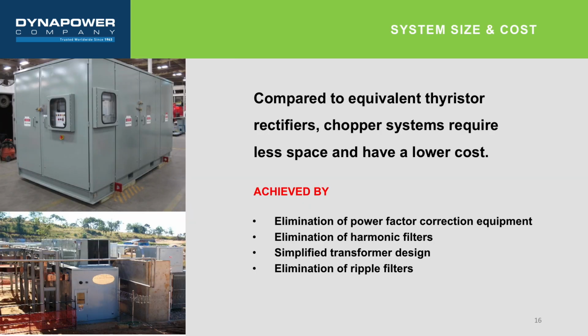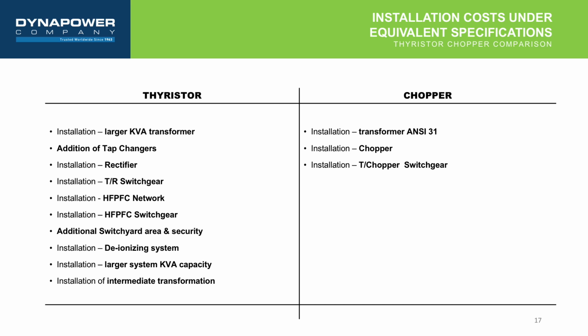System size and cost. Compared to equivalent thyristor rectifiers and harmonic compensation equipment, chopper systems require overall less installation space. A major part of the cost of the system comes from magnetic components, especially the transformer. With the reduction of additional equipment and modular designs, the installation of the equipment is simplified. Chopper-based systems are easier to install and are up and running faster than their thyristor counterparts. The initial purchase cost of the chopper rectifier system is typically less than thyristor rectifier systems with harmonic filter and power factor correction system combined for equivalent operation. Long term, with higher efficiency, lower losses, lower input power consumption, higher power factor, and easier maintenance, chopper rectifier systems are economically much better and more efficient than their thyristor counterparts as well. Let's compare the installation requirements for a thyristor and chopper rectifier.